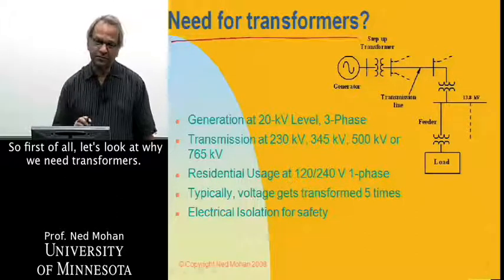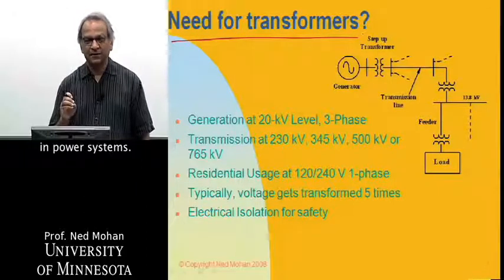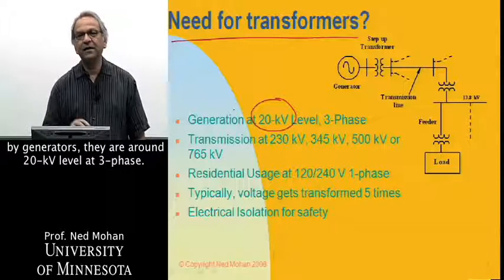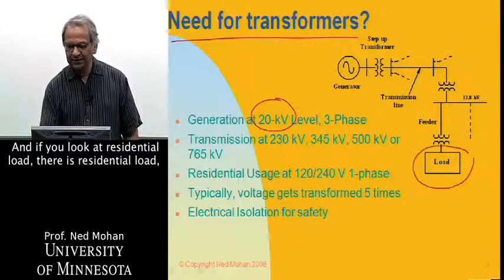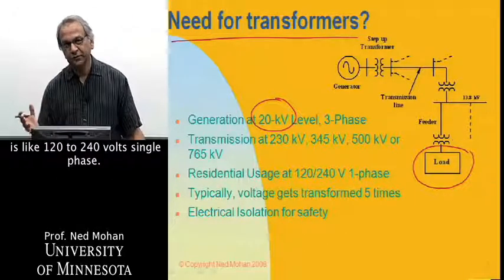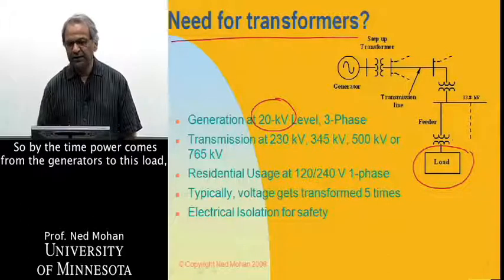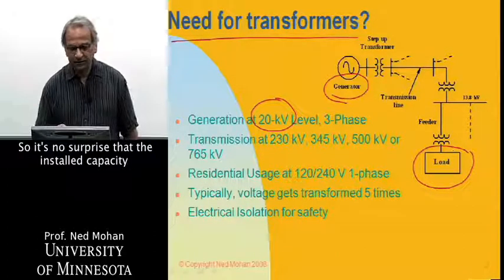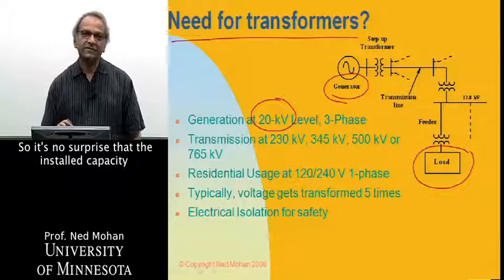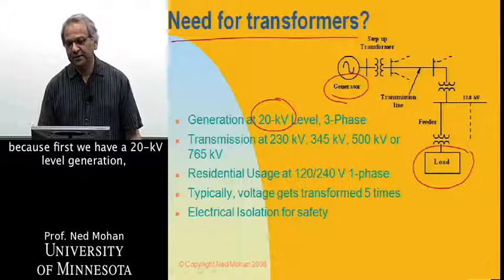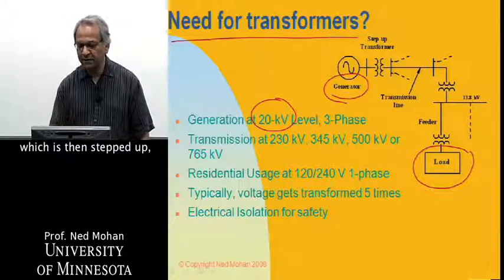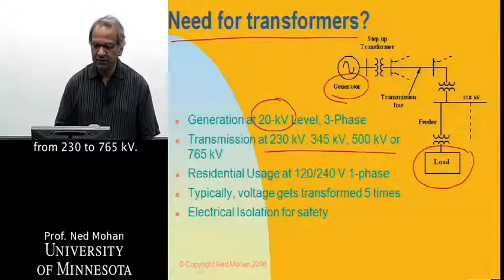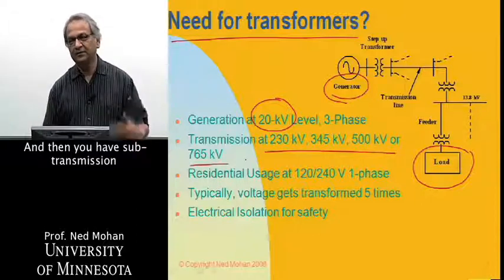First of all, let's look at why we need transformers. Transformers are a very essential apparatus in power systems. If you consider that the voltages produced by generators are around 20 kV level at three phase, and residential load is like 120 to 240 volts single phase, then by the time power comes from these generators to this load, it has gone through approximately five transformations. So it's no surprise that the installed capacity of these transformers is five times that of generators. First we have 20 kV level generation, which is then stepped up, because that's a very low voltage for high power transmission. Then transmission line voltages could be anywhere from 230 to 765 kV, and then you have sub-transmission and distribution system.